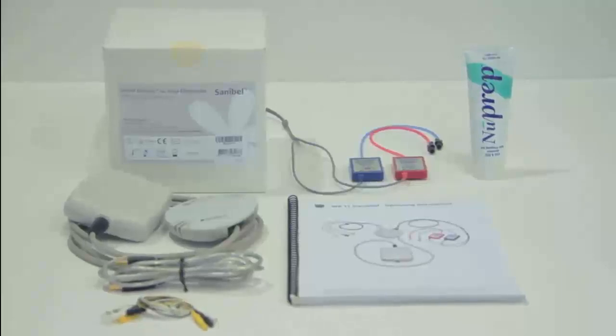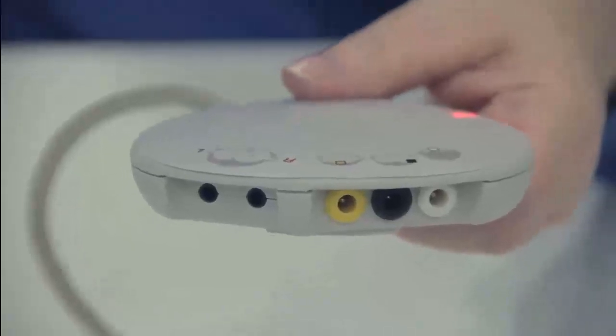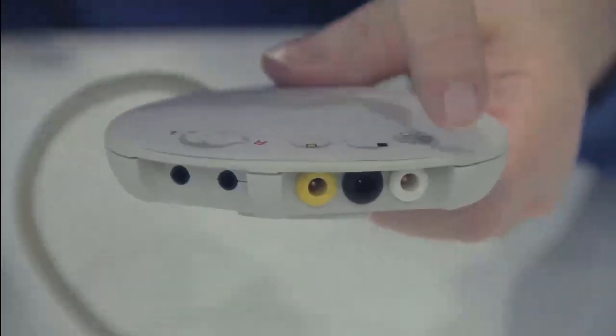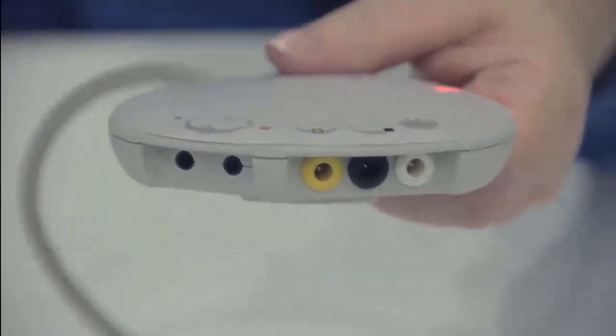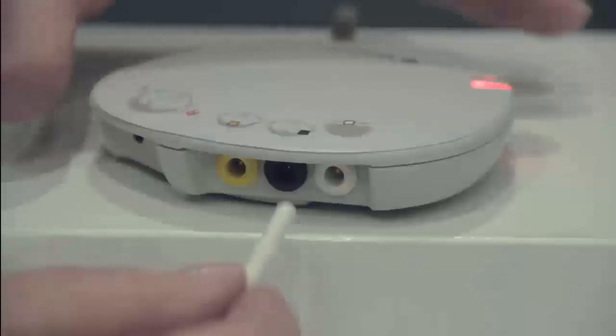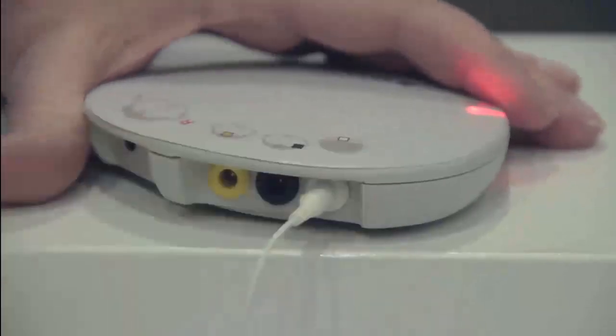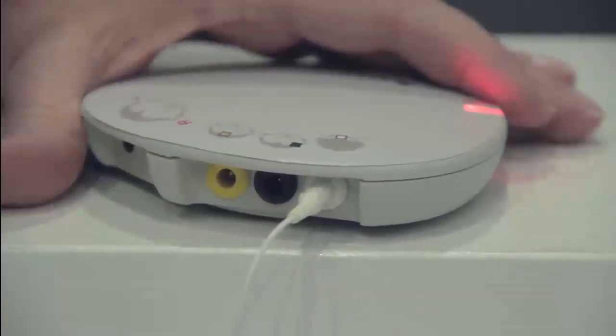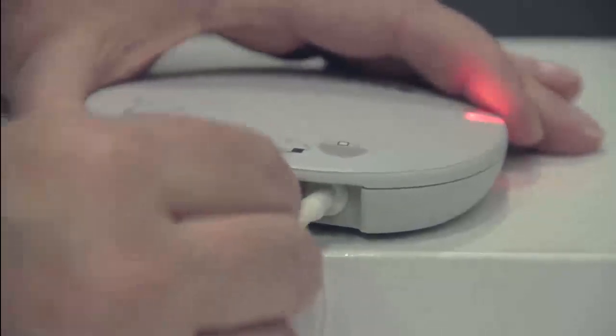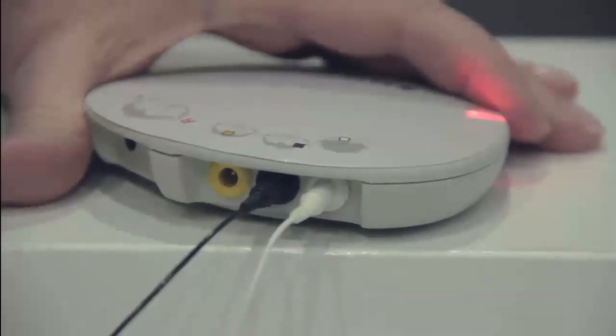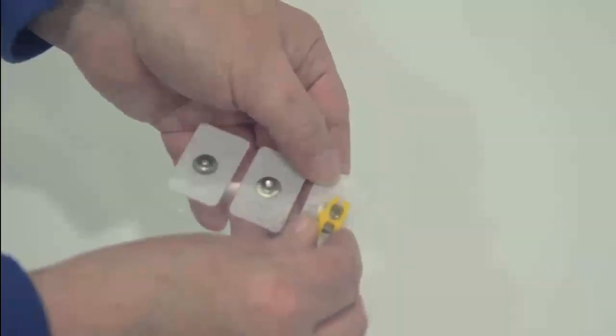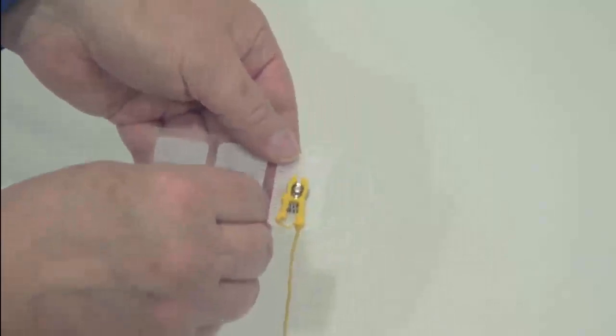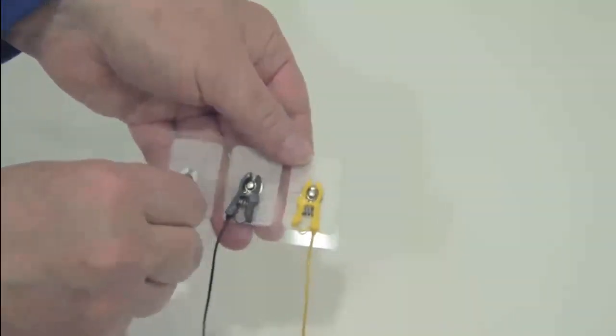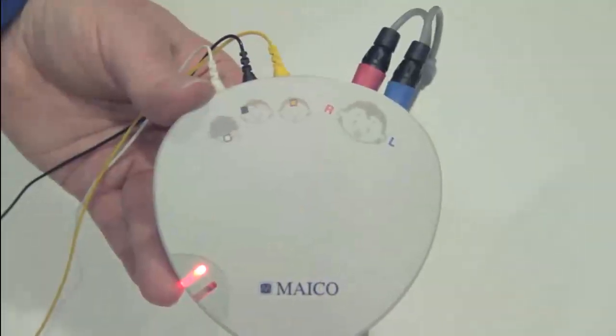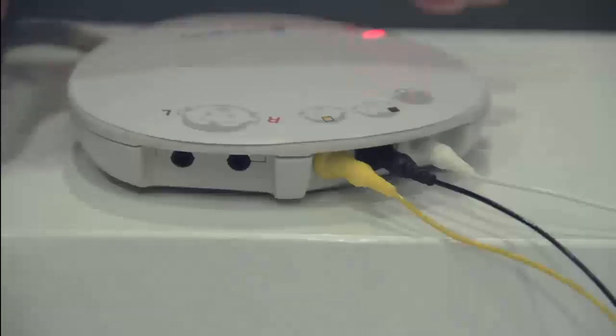The MB11 Classic hardware includes a preamplifier module that contains jacks for the connection of 3 electrode wires and the right and left earphones. The electrode jacks are color-coded to match the color of the electrode wire. Make sure that the connector on the electrode wire is fully inserted into the jack of the same color. Disposable snap electrodes are connected to the end of the electrode wires, getting them ready for placement on the baby. The proper connections for the earphones are shown on the preamplifier label.